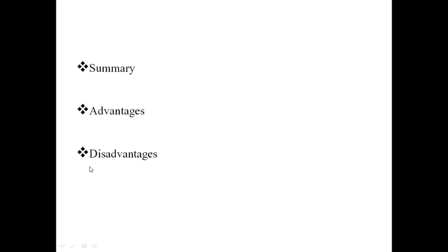Lastly, disadvantages of the thermospray interface. First, if a buffer is present in the HPLC mobile phase, and this is essential for true thermospray ionization, it should ideally be volatile, and this may necessitate modifying existing HPLC methodology.